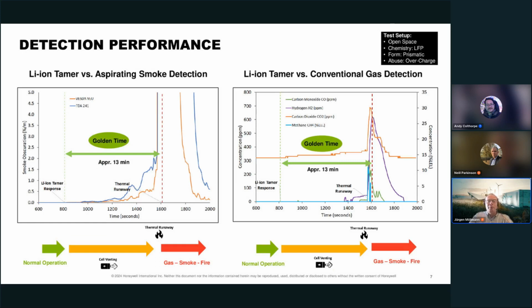Now we have a comparison here related to the other technologies. As you see here, the green dotted line is the Li-ion Tamer response, which is approximately 13 minutes before thermal runaway, which is the red dotted line, where we have the temperature increase during the thermal runaway. Aspiration smoke detection, the blue line and orange line, detects only closer to the thermal runaway. We have done other tests where it's together with the temperature increase of the thermal runaway or even after the point of the thermal runaway.